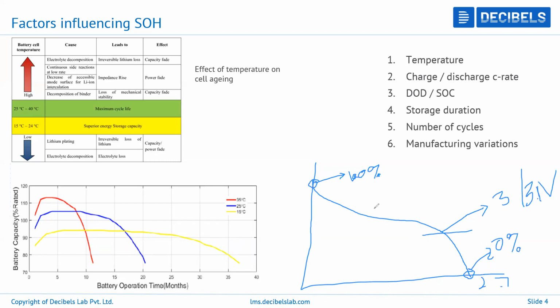Cycling the cell between these values will cause it to last longer. So always maintain a responsible, sensible DOD. We should never go for 0 to 100, 100 to 0 - that gives very low cycle life, somewhere around 500 to 800 cycles if you're going for full DOD. But this can give way more than 1200 to 1500 cycles if you keep the DOD within something like 85% down to about 20-25%.